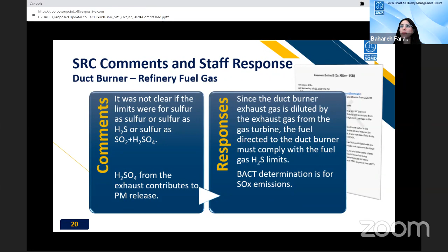But because of diluting this exhaust with also the gas turbine exhaust, we use the first method, measuring the sulfur directly in the fuel gas. And the last comment is H2SO4 from the exhaust contributes to PM release. So we just want to clarify that this BACT determination is for SOx emissions. So we are not looking at the PM release right now. It may affect that, but this is specific to the SOx and we specified in the BACT determination form.